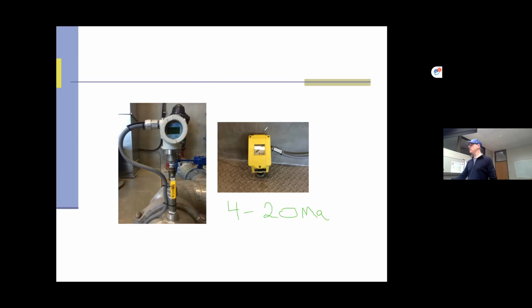It's important, so instruments are dumb. They don't know if they're measuring pressure or level. They have no idea. All they're doing is taking a signal from the thing that they're measuring. They have no idea what it really means. And all they're doing is making a 4 to 20 milliamps. At 4 milliamps, it always means zero, zero of whatever it's going to be. And at 20 milliamps, it's going to be the maximum of the scale you choose. So a 4 milliamp signal means zero, and a 20 milliamp signal is maximum. And that's why they call it the 4 to 20.